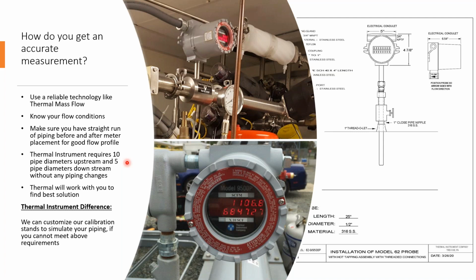Other things to keep in mind is, where is the meter going to be situated? Do you have a straight run before and after the meter? Because any instrument in any measurement environment typically will require some straight run before it and after it so that you get a good flow profile going past the meter sensors. So you can see what we list here. We typically require 10 piping diameters upstream of the meter placement and 5 after the meter placement without any changes. But the one thing that we can do that maybe some other people can't do is that if you don't have that, we can maybe customize our calibration stand to simulate what you do have.